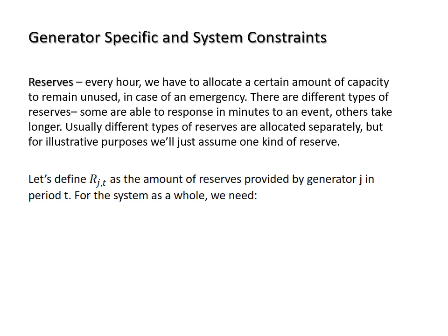One of the other things that we have to make sure we're providing in addition to demand is reserves, right? We've talked a lot in the lecture on shocks and failures about the need to have redundancy built into systems. And we've talked a little bit about what reserve margins are. We have to have extra capacity built into power systems beyond just the forecasted peak annual demand. If the highest electricity demand that Duke Energy ever experiences in the western half of the state is 18,000 megawatts, there's a reason that their entire generating capacity is 23,000 megawatts. It's because they want to make sure that if a power plant fails, there's something online or that can rapidly become online in order to respond to that contingency.